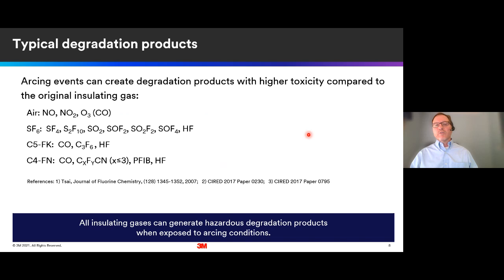So those comparisons were for newly mixed gases, as just first installed into equipment, and what's intended to be in there. However, as Renee described, there is going to be some decomposition that could be generated of any insulating gas when it's exposed to arcing conditions. So a number of the byproducts that could be generated from any insulating gas could be more hazardous than the originally intended insulating gas mixture. And that would pose more of a toxicity risk to anybody that could be exposed to it. So depending on the composition of the gas, you can see different degradation products that are more hazardous that could be formed. And these would vary in concentration depending upon the amount of energy that's put into the gas, so what the actual arcing conditions entail.